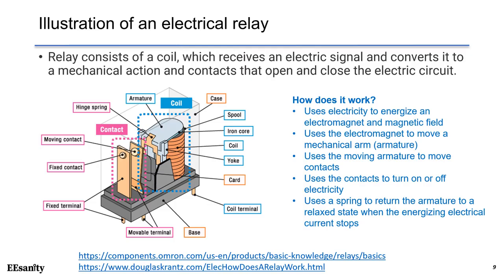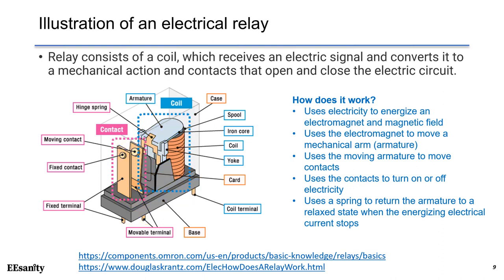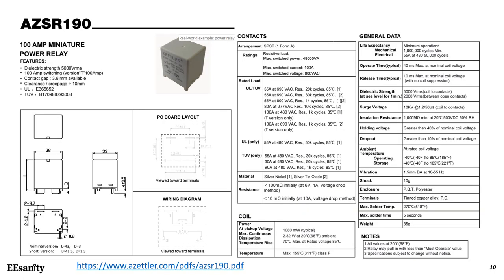The basic design of a power relay utilizes an electromagnet, an armature, a spring, and one or more pairs of contacts. In this illustration, the contacts are used for high voltage and high current applications, which are normally open (NO). When the coil is energized, the contacts become closed and therefore allow a large current to flow through. Basically, it uses a small electric current, typically tens to hundreds of milliamps, to operate the contacts of an electromechanical switch that controls a much larger current in high voltage and high power applications.